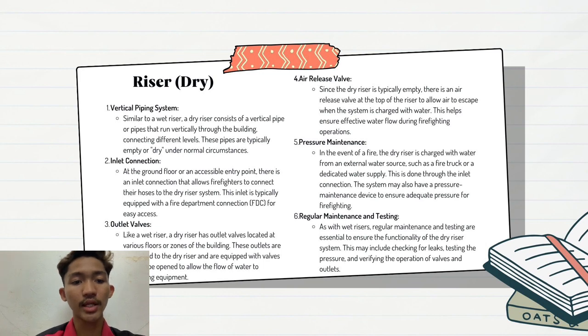This inlet is typically equipped with a fire department connection, FDC, for easy access. Third, the outlet valve. Like a wet riser, a dry riser has outlet valves located at various floors or zones of the building. These outlets are connected to the dry riser and equipped with valves that can be opened to allow the flow of water to firefighting equipment. Fourth, the air release valve. Since the dry riser is typically empty, there is an air release valve at the top of the riser to allow air to escape when the system is charged with water. This helps ensure effective water flow during firefighting operations.